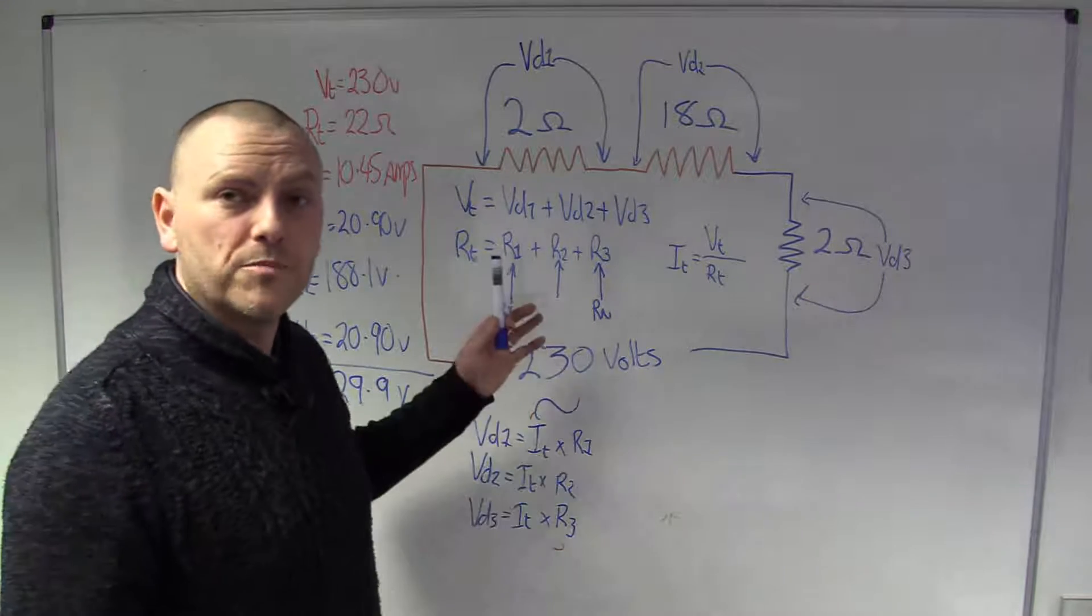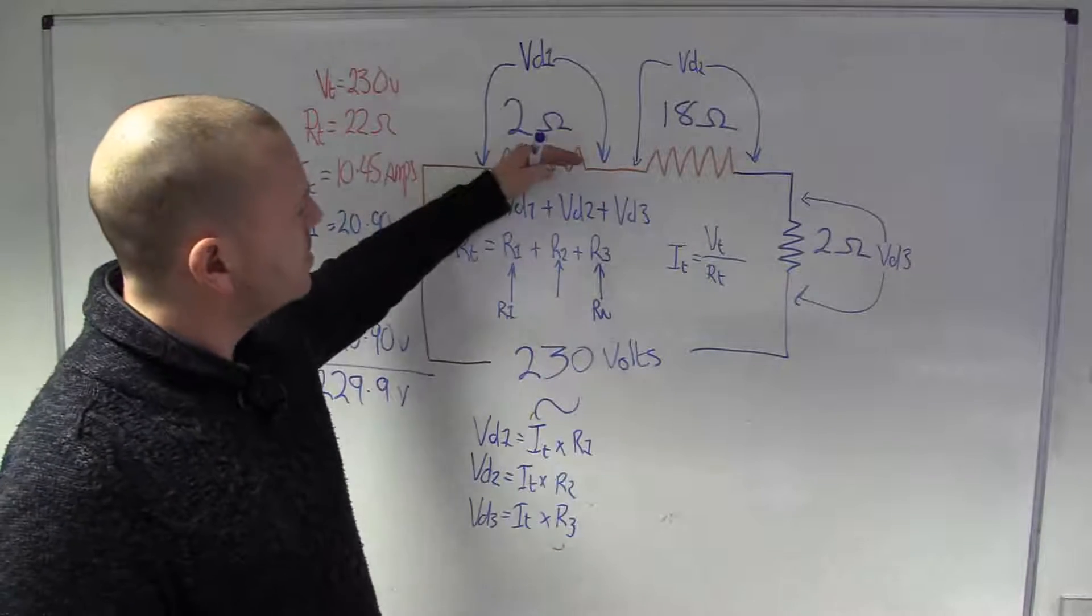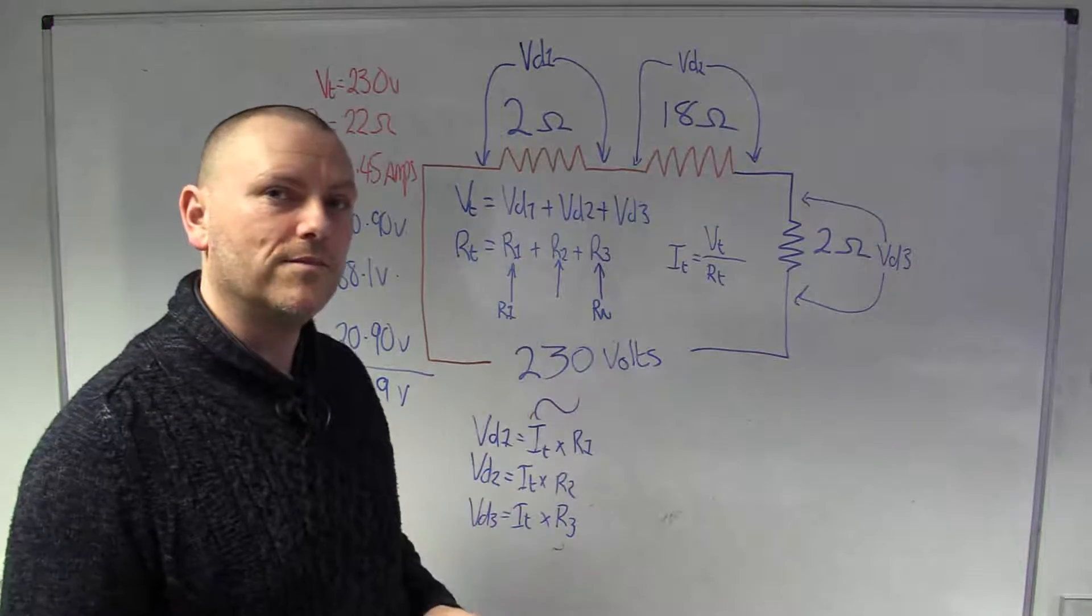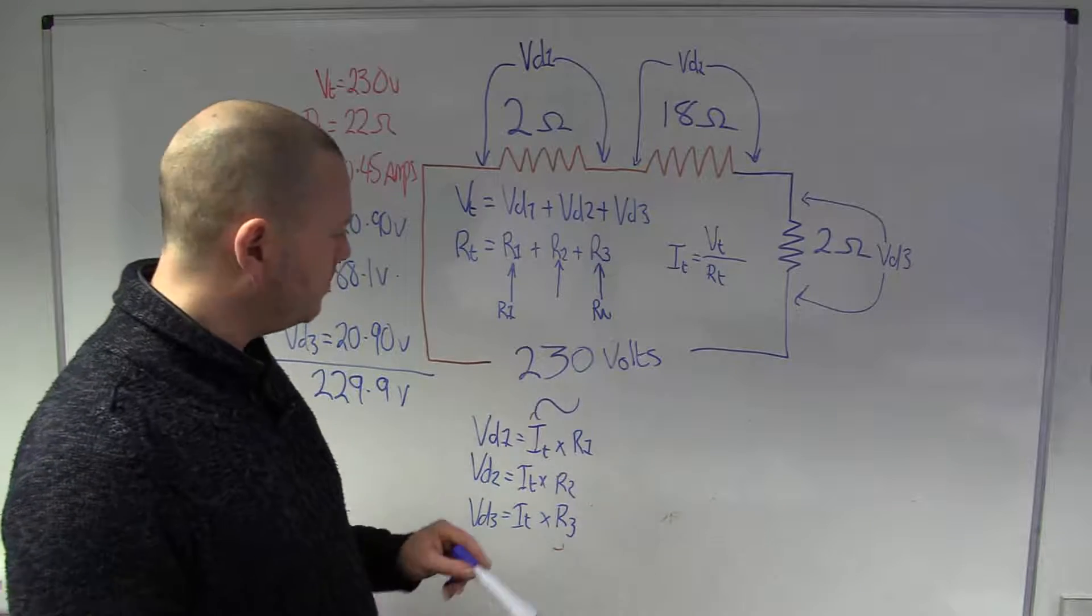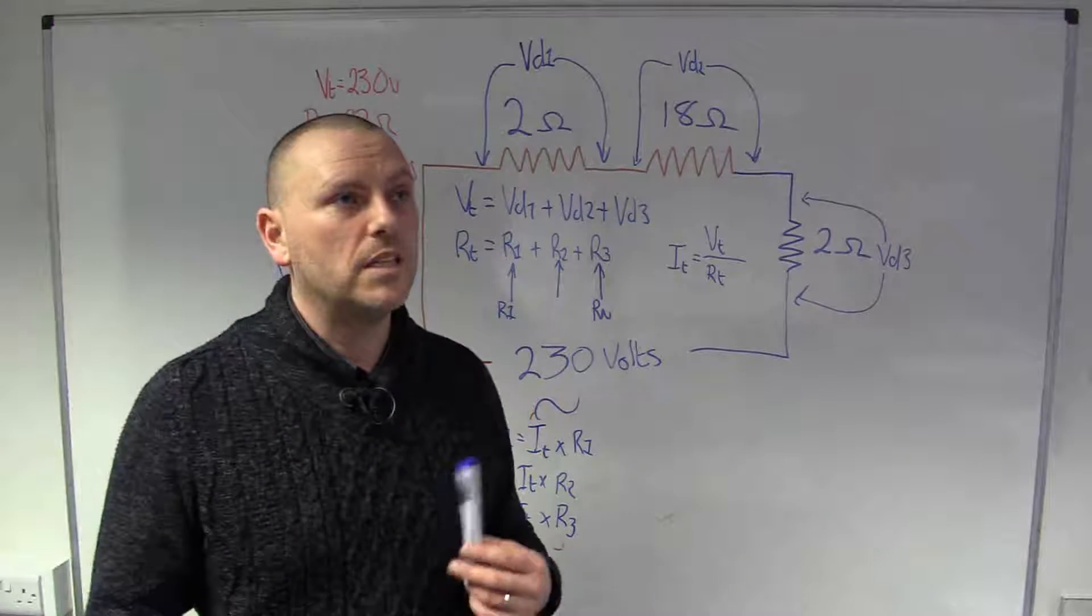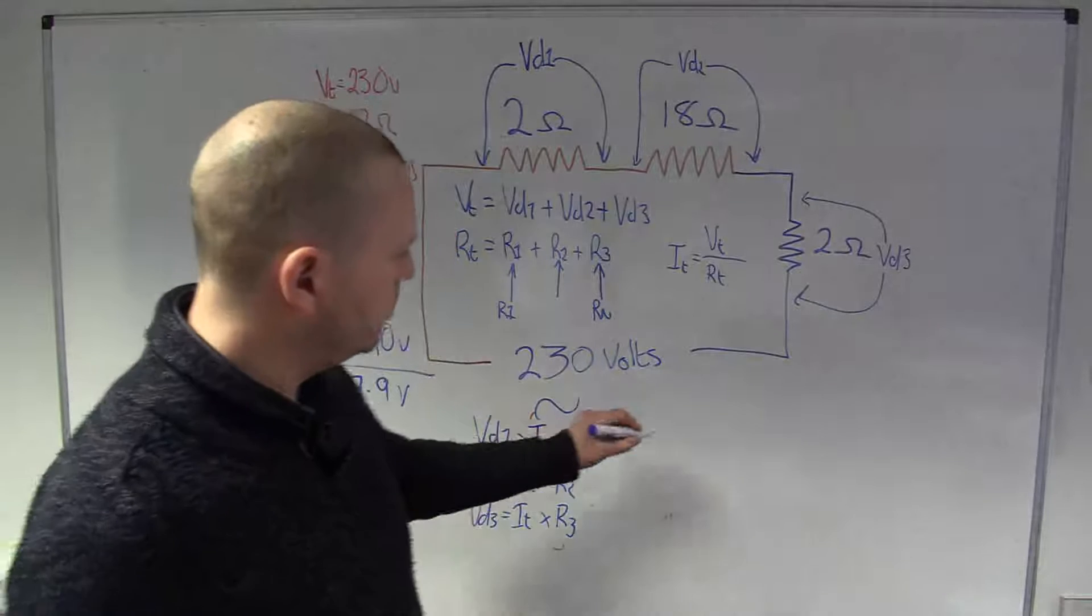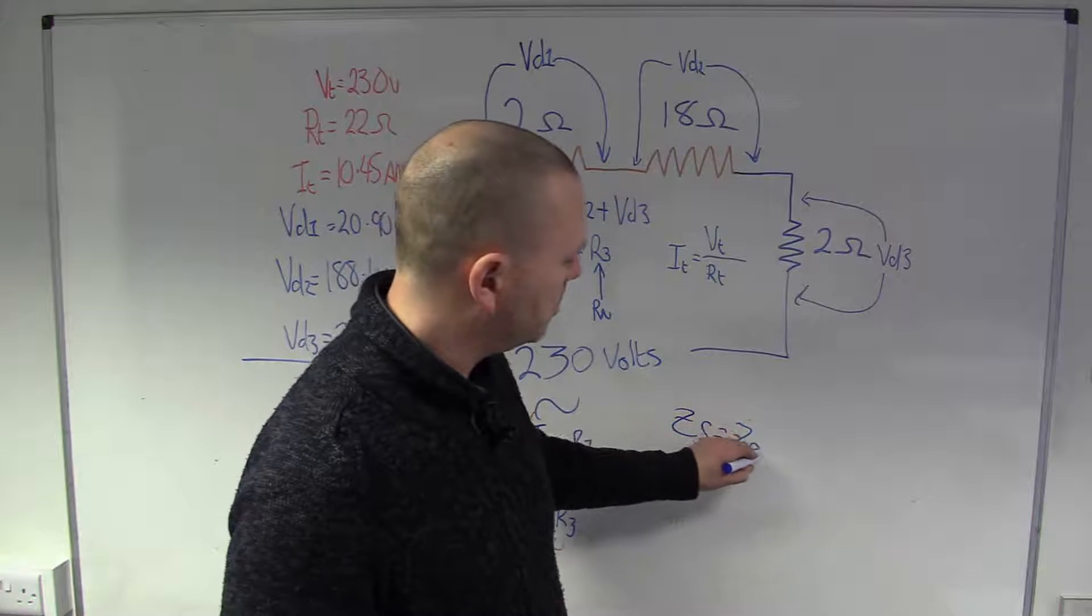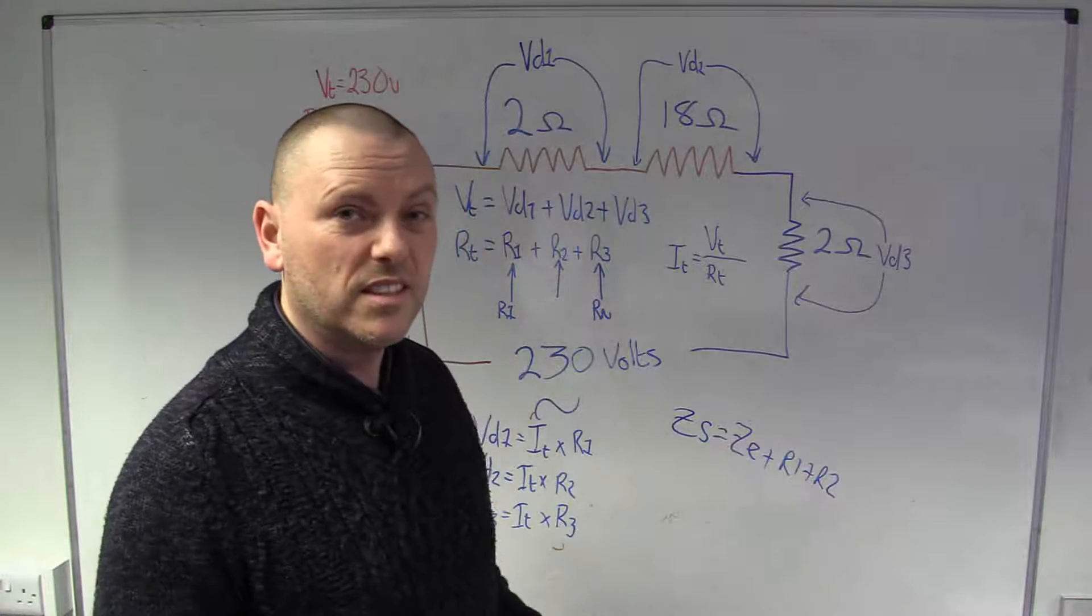So in the real world this could represent an actual circuit we could be adding up the resistance of our live cable, the resistance of our neutral cable and then calculating the volt drop based on the design current, exactly like this really. Or we could be talking about maybe the R1 and R2 measurements. You know when you get into it you'll find this equation pop up quite a lot.